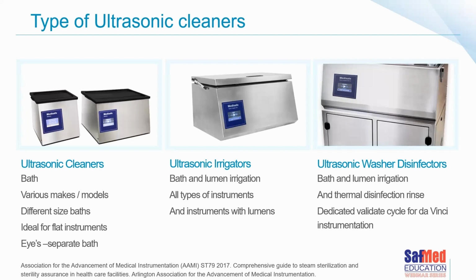And please remember, if you are using ultrasonic cleaners to clean our instruments, please keep a separate bath for our instruments. Don't mix ours with other instrumentation. Then we have ultrasonic irrigators, which is a bath with a lumen irrigation component to it, designed for all types of instruments, especially instruments with lumens, because of that ultrasonic irrigation, that lumen flush that is so critical. And that's how we're going to clean some of those really complex devices.